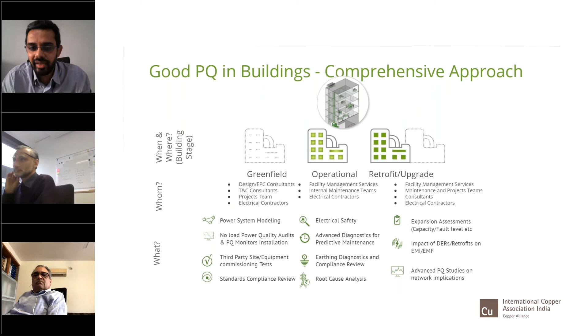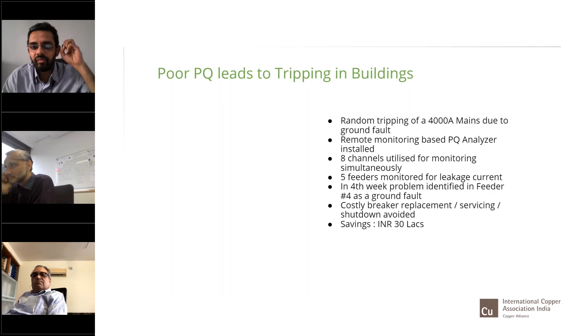but I want to quickly take you through 3 or 4 live examples that can throw much faster light on this. The first was a case of a building with random tripping of a 4,000 ampere main due to a ground fault. Remote monitoring was done using a power quality analyzer — you see the graph on the left, where we monitored 8 channels simultaneously. The graph may not be fully visible, but this shows the voltages: line to line, line to neutral, and neutral to earth voltage, along with frequency. The remaining channels were devoted to current — the first 3 channels were of the main breaker facing the tripping, and the next 5 channels monitored the leakage or zero sequence current of different downstream feeders installed in the facility.